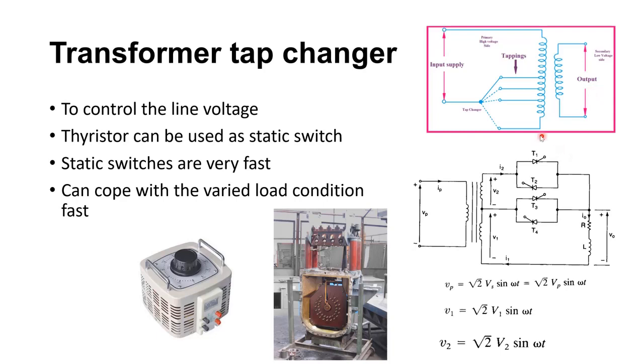Okay, so instead of a mechanically rotating switch like this, it can also be controlled using thyristors, by using them as a static switch, as shown in the figure here. In the primary we have the primary winding, and in the secondary we have these tap changers. In this particular example we have two different tap settings. One is here and the other is connected here, and we have two thyristors placed in anti-parallel direction. Depending on our need, we may connect this part, or this part, or both, depending on the scenario. You will see it.